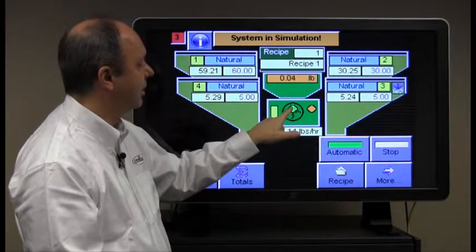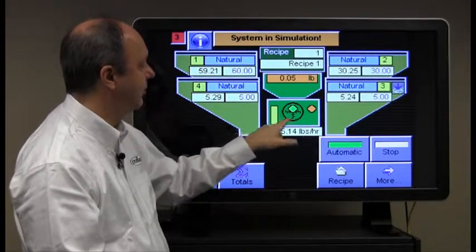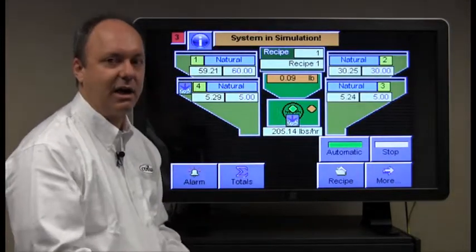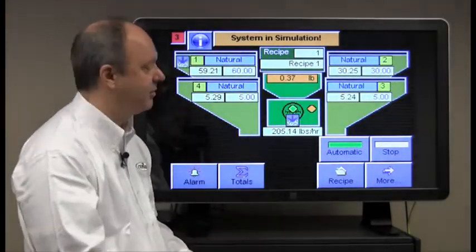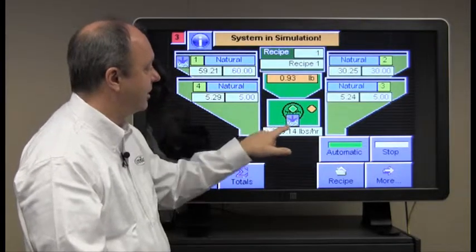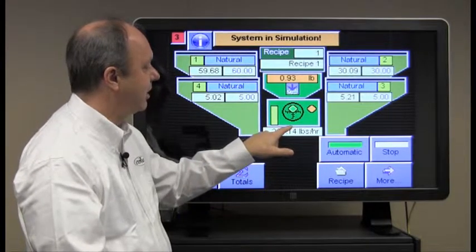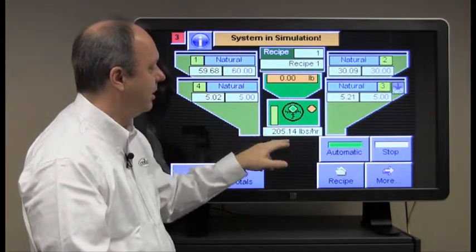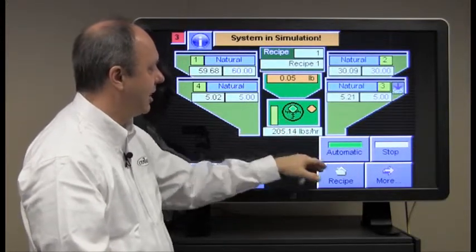The green light on the mixer comes on indicating the mixer is turning and this yellow bar indicates that the proximity sensor inside the mixer has been covered. After it's mixed it, the arrow appears here indicating that the gate at the bottom of the mixer is opened and dumped the mixed material into the process.